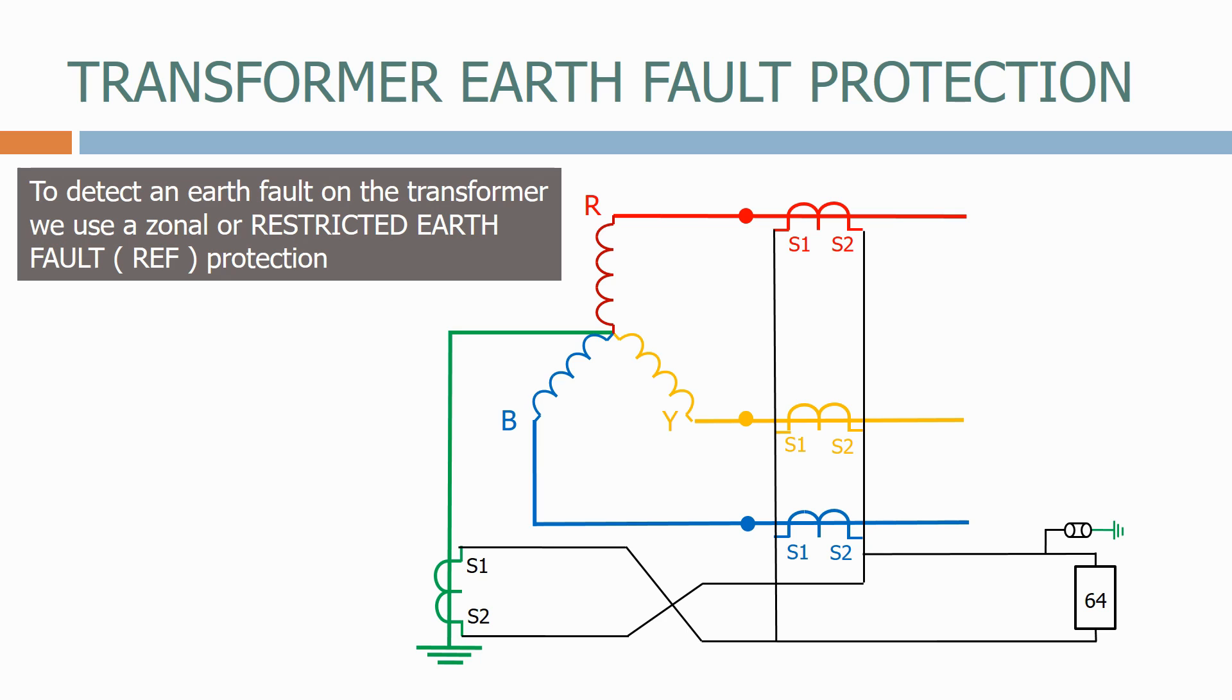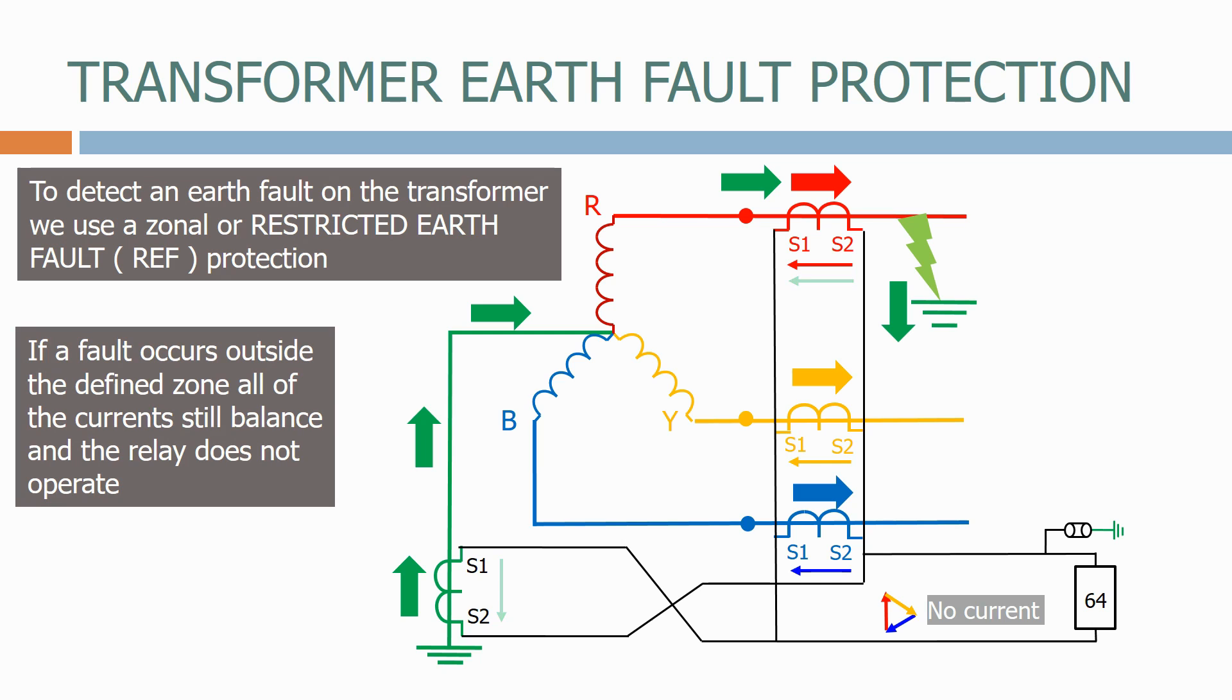Let's now energize the transformer. Let's now apply a fault on the red phase outside the zone and see what happens. As expected, we now get additional earth fault current on the red phase. This is now balanced by the current detected by the CT on the ground connection. If a fault occurs outside the defined zone, all of the currents still balance and the relay does not operate.